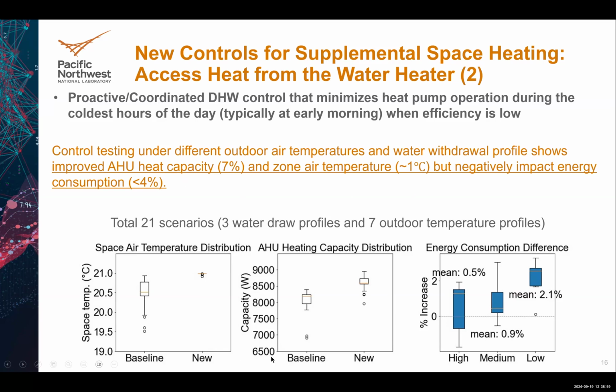So if you look at this sub-box plot, we compare the baseline with our new controls. For the temperature, we have the set point at 21. Here we show the AHU heat transfer rate increase for the new control. Overall, we got an average improved AHU capacity of about 7%. The zone air temperature can be improved by around 1 Celsius, but we have a negative impact on energy consumption. So that's the trade-off, right?